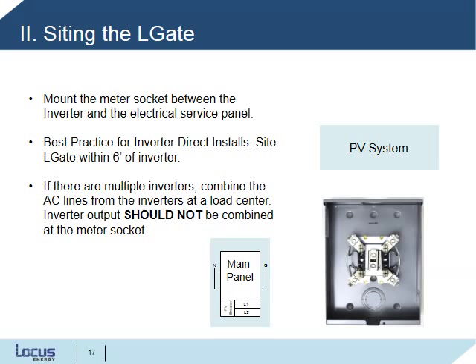With these considerations in mind, the first step in the actual installation is to mount the meter base between the inverter and the service panel. Now, the RS-485 cable attached to the base of the LGate 120 and 320 is 6 feet in length. If you'll be setting up inverter direct monitoring, we recommend siting the LGate within 6 feet of the inverter, so you won't need to extend that RS-485 cable. Now, if there are multiple inverters, it's important to combine the AC loads at a load center and not at the socket itself.